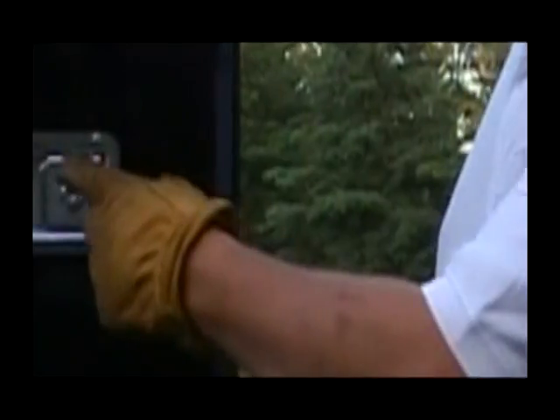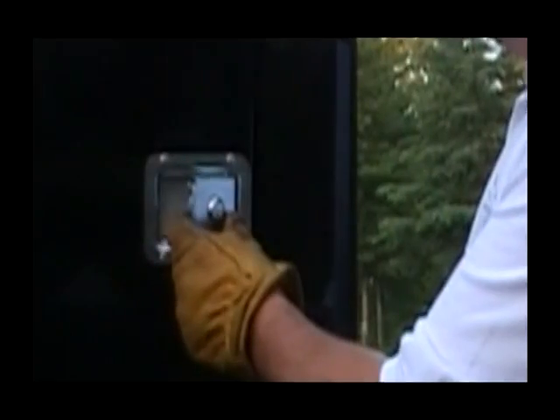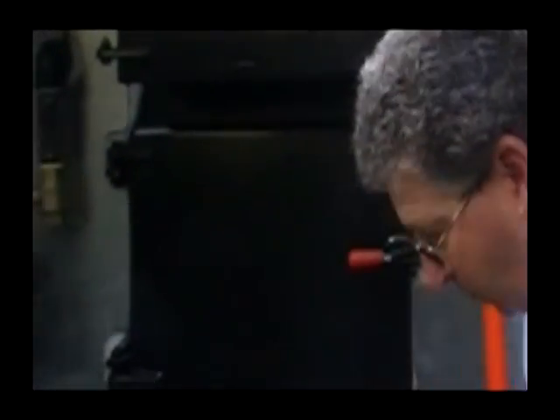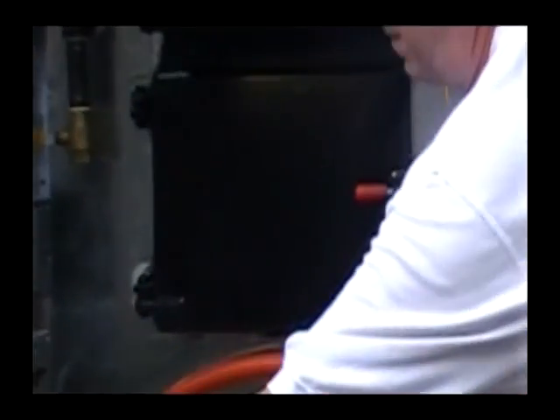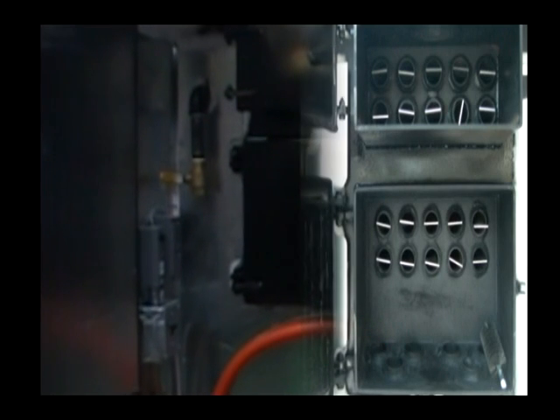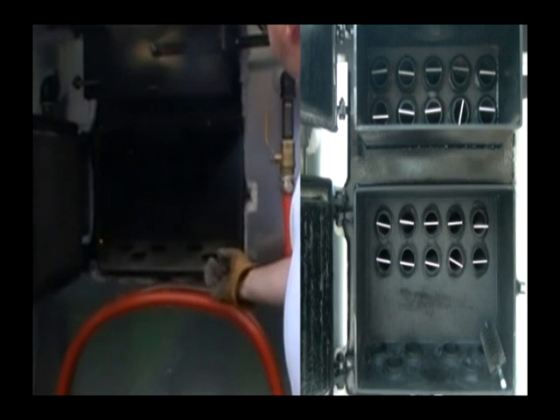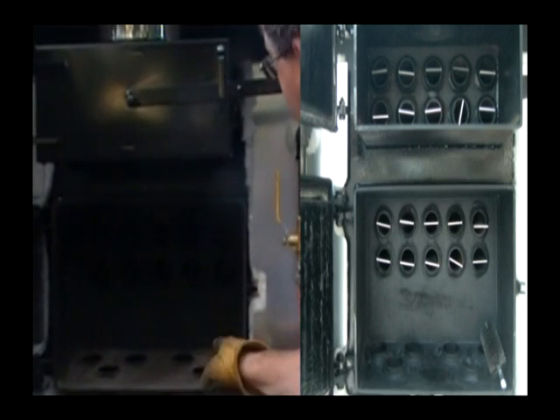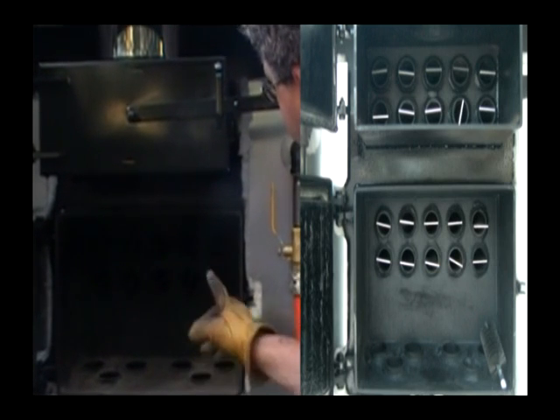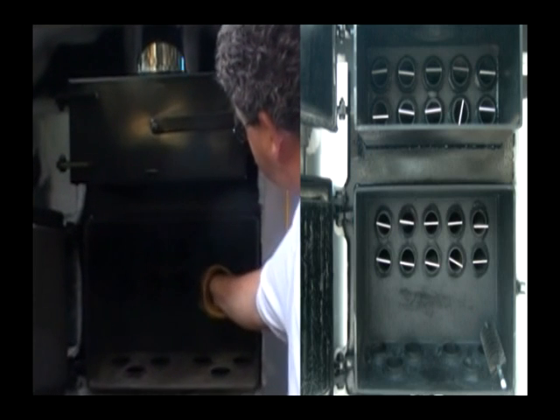Here we're going to go into the back access doors to the back end of our stove. Nice large paddle lock latches, large doors, easy to access everything in the back end of the stove. We have the access door to the second and third pass of our heat exchanger. Adjustable latches, easy to open and close. The heat comes up through these 6 tubes of 2 inch in size. It does a 90-degree turn and goes to the front through these 10 tubes with turbulators in them. Easy to pull out the turbulators to dust out. We just brush them out once in a while.